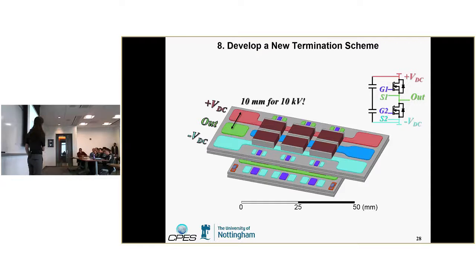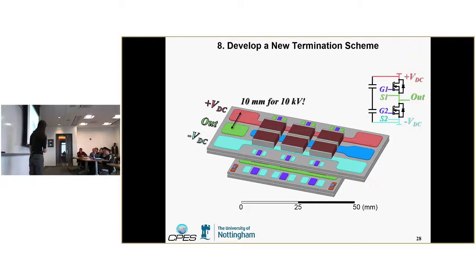But one of the issues is termination. You've got 10 millimeters now for 10 kV, so how do you terminate that? How do you connect it to the rest of your system? This is a huge issue. If you look at most power modules, they use bus bar connections, and at higher voltages you need to worry about creepage and clearance distances and standards, which significantly increase the size of your module. For 10 kV you need about 80 millimeters of spacing, but the power module itself is only 50 millimeters. That's not possible, so we're looking at new termination schemes.